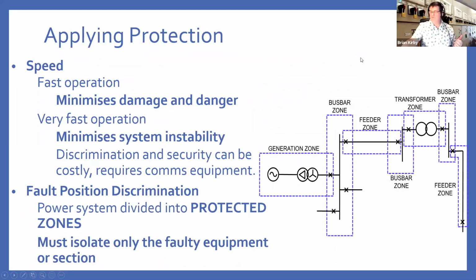So if we come to look at the application of protection, speed is a key factor in our network. And the higher the voltage, generally, the faster you want to be able to clear your fault, because the more energy that is likely to be flowing through your system at that point. So fast operation will minimize danger and damage to the system. Very fast operation, and by that we're talking sub-cycle, so less than 1 power system cycle, which is 20 milliseconds in the UK. That is usually for transmission systems, and it's to maintain stability.